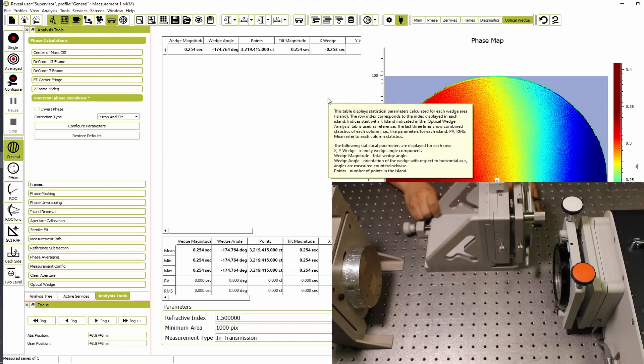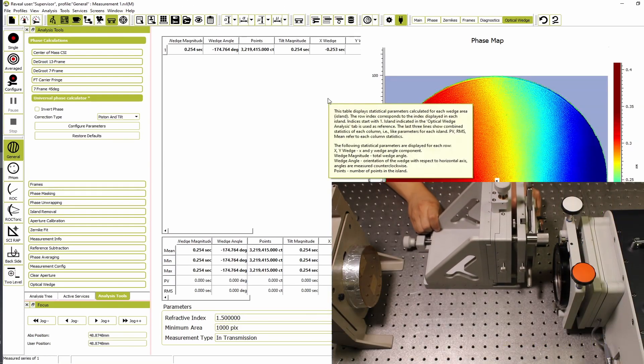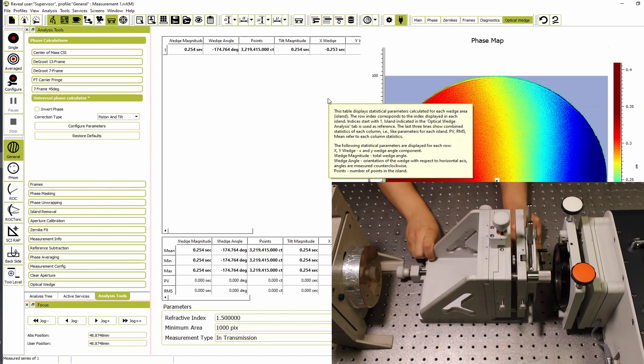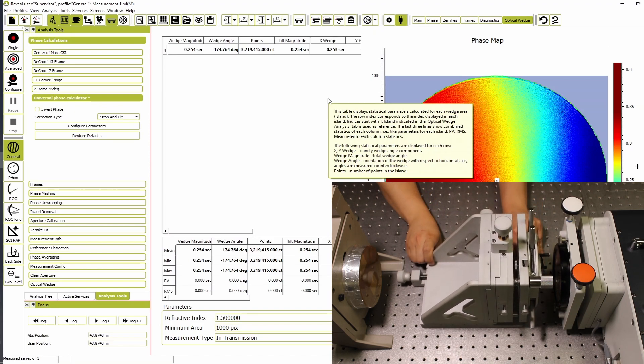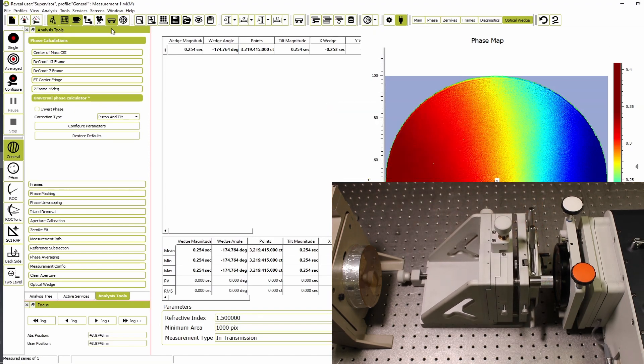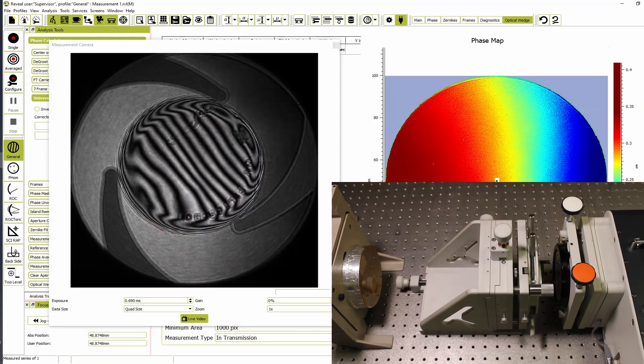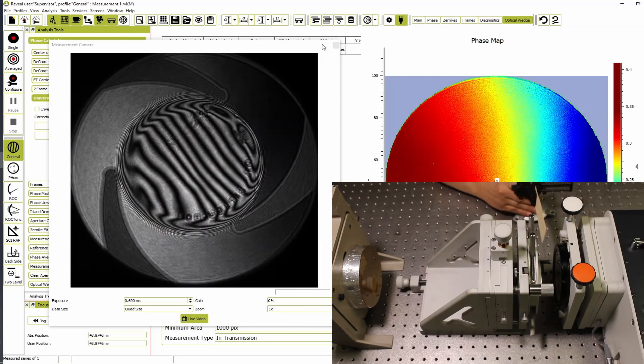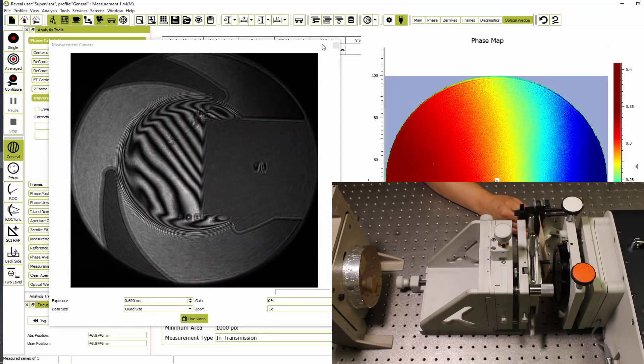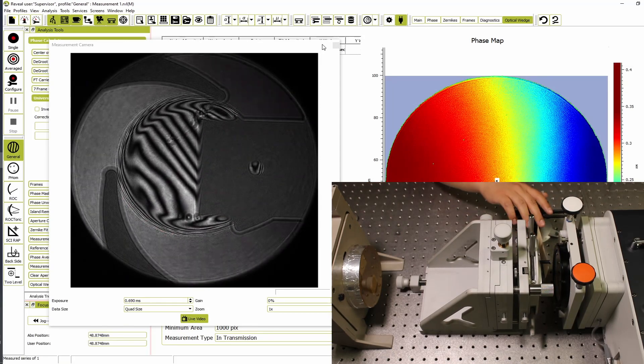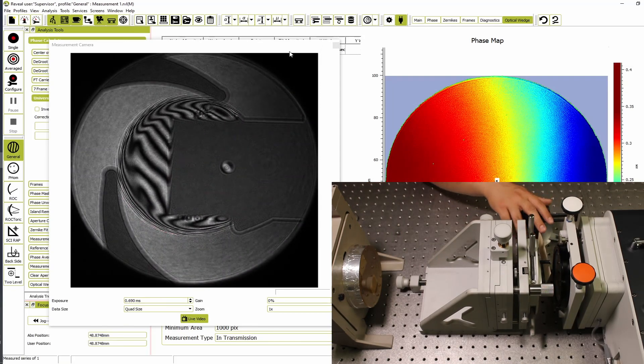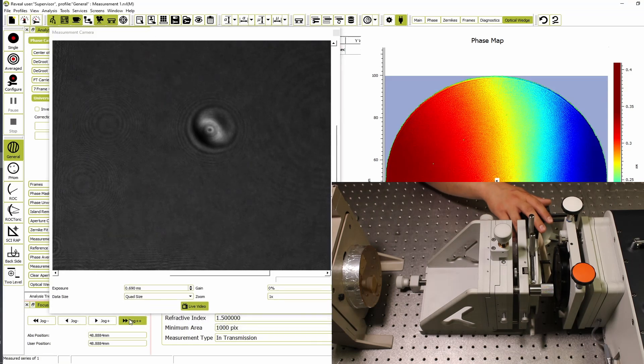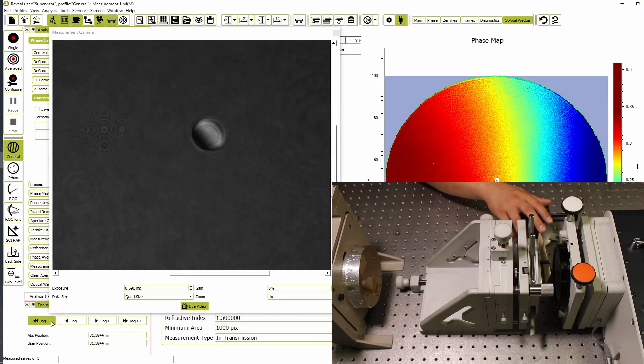Introduce the wedge to the optical cavity. Make sure there is no reflection coming off the part by tilting it away from the camera. Using the stage controls, focus the camera on the wedge. The camera may be particularly difficult to focus, especially if the measurement is in reflection.